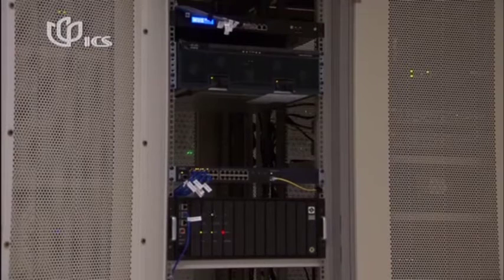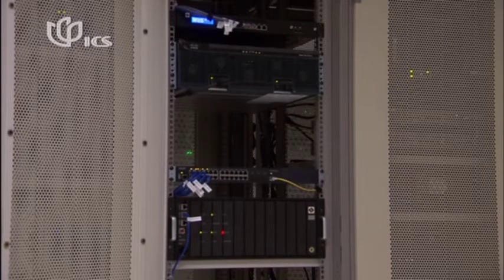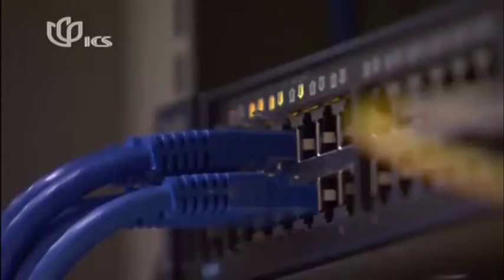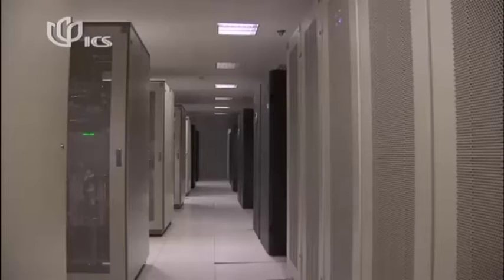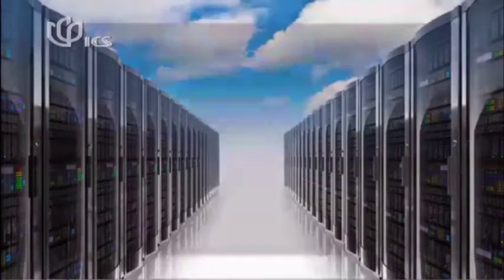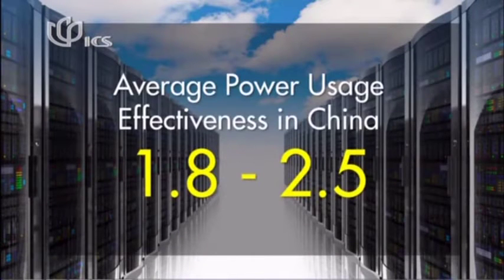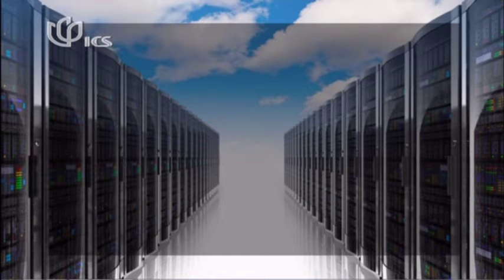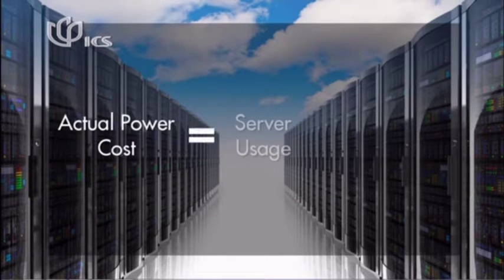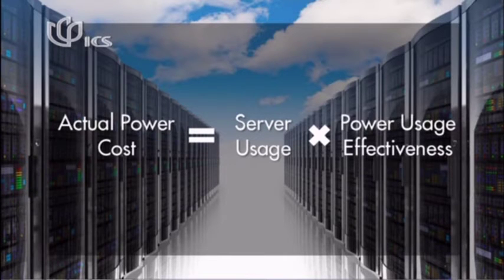A fully occupied rack of servers will consume 15 kilowatts of electricity per hour, and that puts out a lot of heat. Keeping everything cool becomes crucial, as servers have to be kept at a temperature of between 18 and 27 degrees. The average power usage effectiveness, or PUE, of data centers in China is between 1.8 and 2.5, meaning the total power cost of running the center is 1.8 to 2.5 times the electricity cost of the servers themselves.